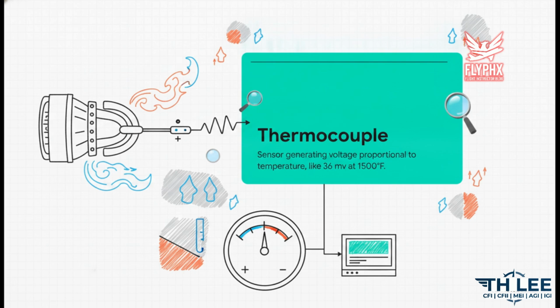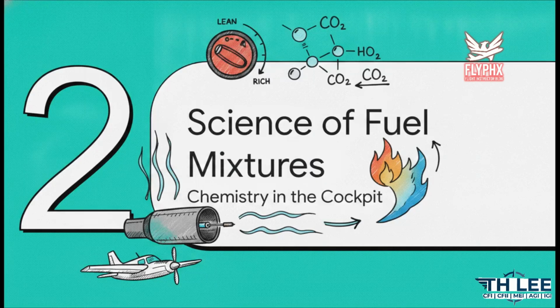What's truly fascinating is how we process that tiny signal. Digital EGT systems physically amplify this minute voltage to give you incredibly precise temperature readouts. But traditional analog instruments, they just read that raw voltage directly. That's exactly why those older gauges often don't have specific calibration numbers on their face. They're just showing you a raw electrical swing. Section 2, science of proper fuel mixtures.